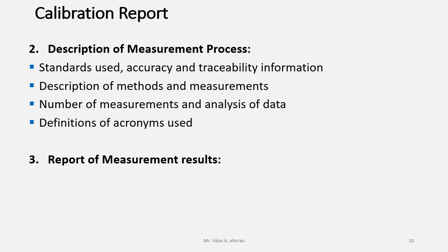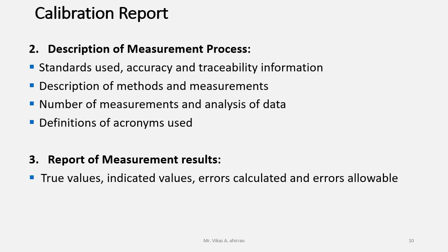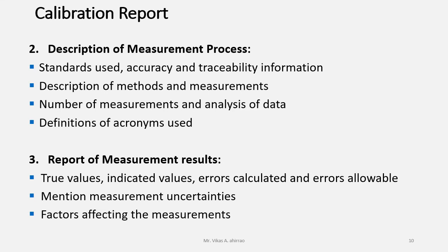The third part will give the report of measurement results. It will consist of the true values, the values indicated by the instruments, the different errors that are calculated, and errors allowable. They should mention the measurement uncertainties. Also, the various factors that may affect the measurement are mentioned under part 3.